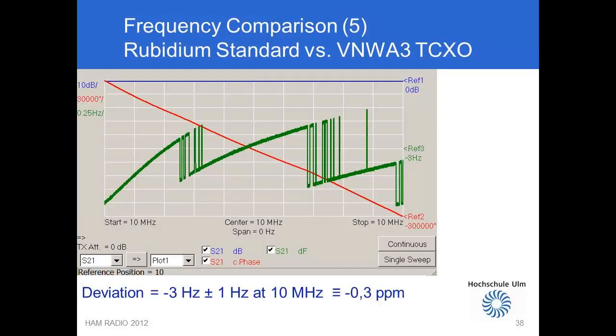Here you see a quite dramatic plot. I have measured the internal VNWA3 TCXO against the Rubidium standard. The green trace shows the frequency difference, and it looks quite dramatic, doesn't it? Just pay attention to the frequency resolution being set to 0.25 Hz per division. In total the frequency offset is minus 3 Hz, equivalent to minus 0.3 ppm. The specification of the TCXO is 2 ppm, so it's okay.